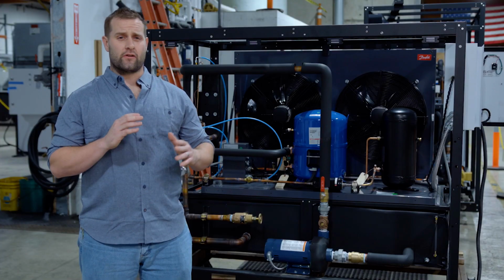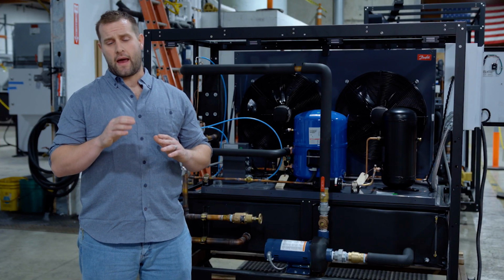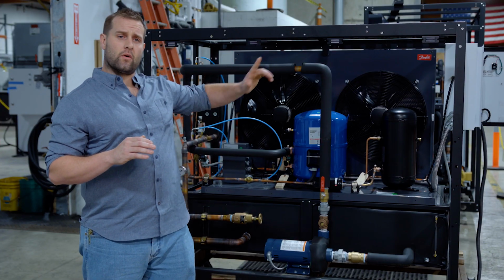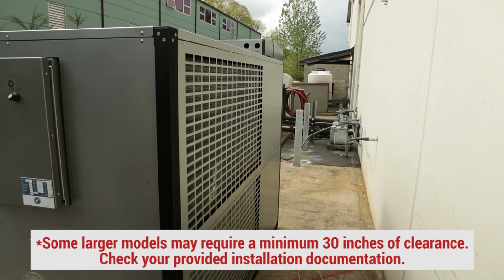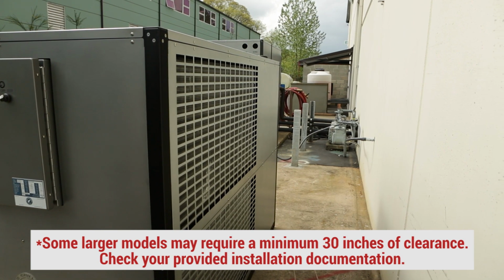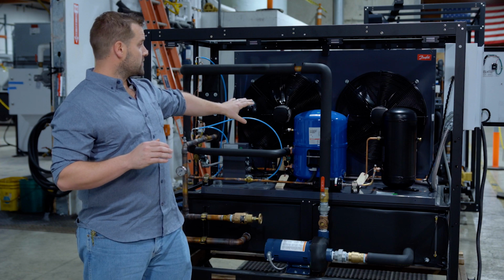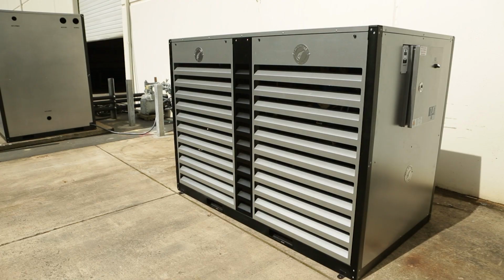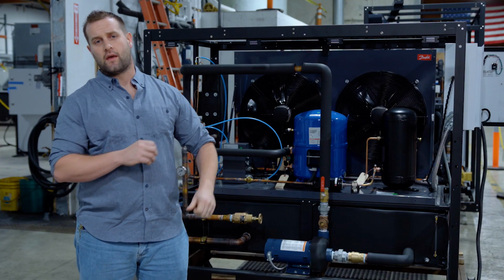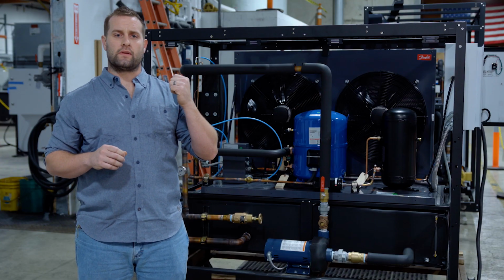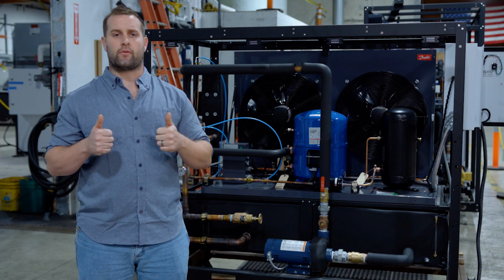As far as the clearances go, it's very important to get this right off the bat. On the intake side, on the back side of the chiller, you want at least 2 feet of clearance. On the front side of the chiller with the louvered panels, you're going to want that completely open to free air. You don't want any of the hot air escaping from the fans to get recycled back into the intake of the condenser and spike your head pressure.